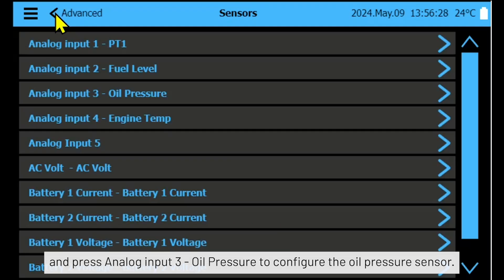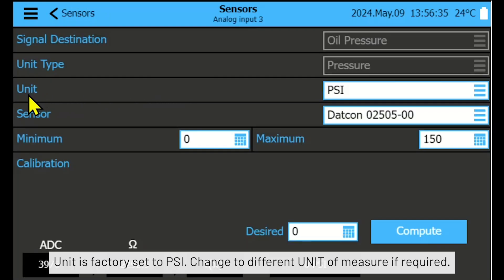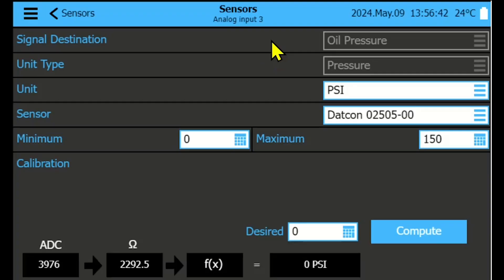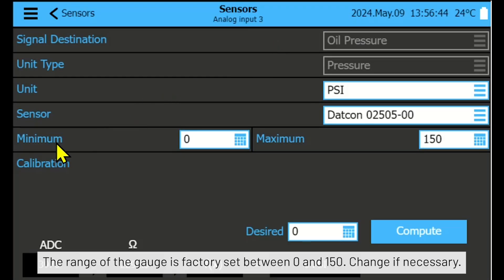Press the back arrow and press Analog Input 3 — Oil Pressure to configure the oil pressure sensor. The unit is factory set to PSI; change to a different unit of measure if required. The range of the gauge is factory set between 0 and 150; change if necessary.